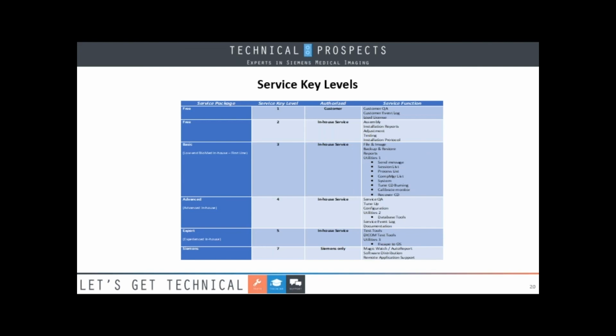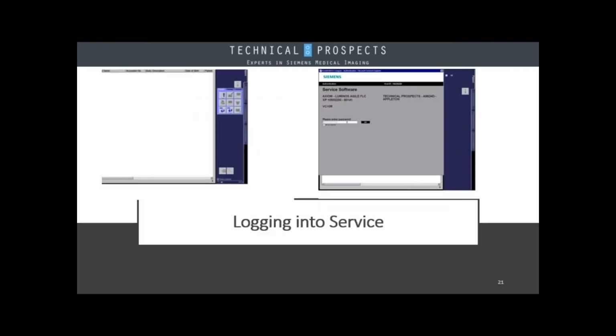Otherwise, they're not going to give you one. So if you get a service key, here's what you can do with it—this is off of my company's Luminos Agile. The first one is an operator screen when you walk in. You hit that top service button and that screen will pop up. If you have the first 14 digits of the 20-digit key, great. If not, put in your first 14, hit the set as default box, then put in your last 6. Once you do this, you shouldn't have to do it again, just the last 6.